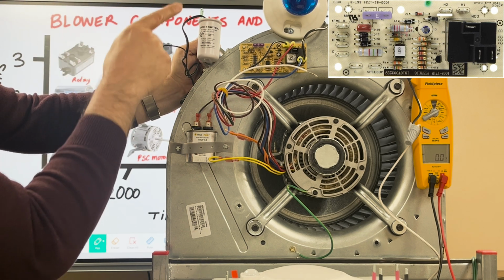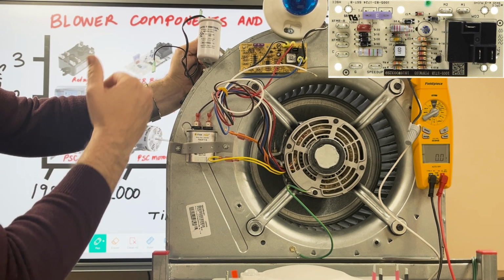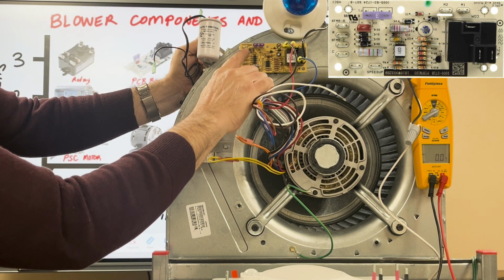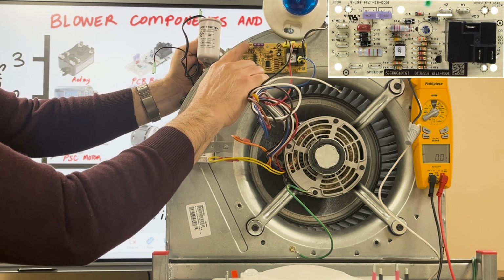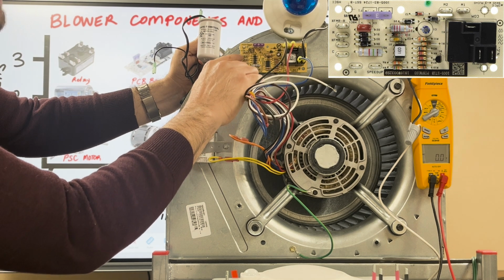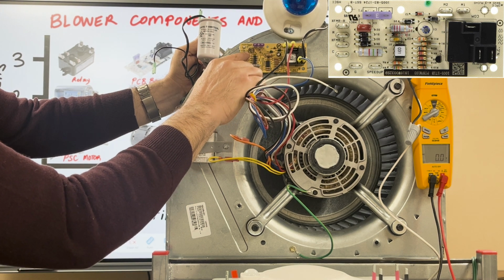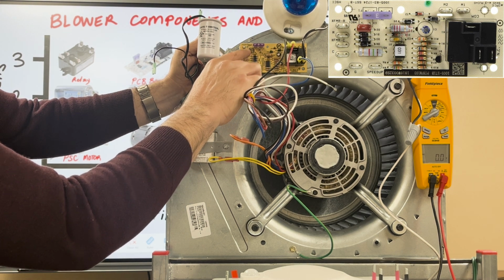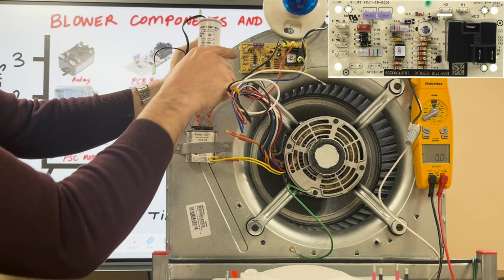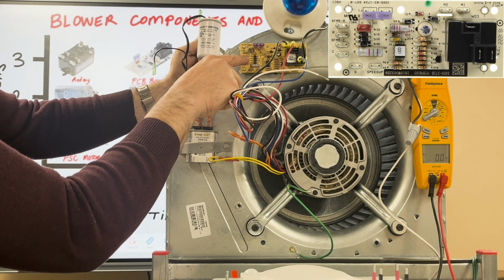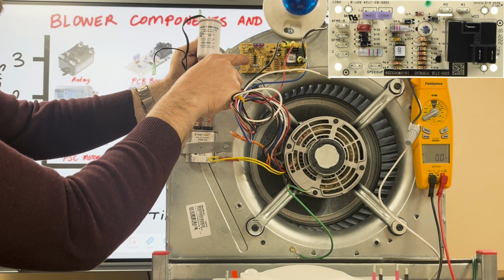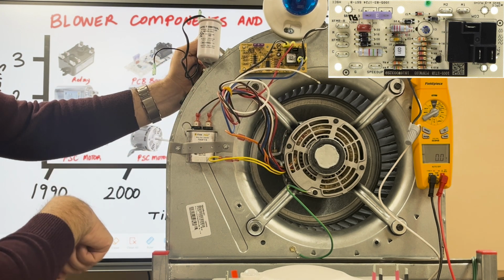If you look over here on the top left-hand side, we have a picture of the board again so we can talk about each terminal as we go down. On the top left, I have my transformer power in, then underneath that I have 24 volts primary coming out, and underneath that I have my transformer common, going back to the transformer.